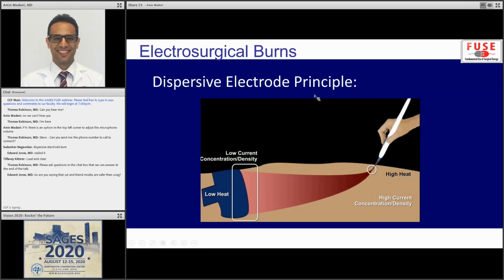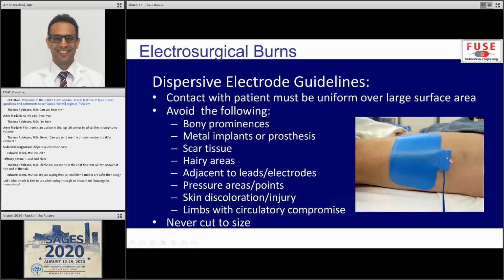The dispersive electrode is designed with a large surface area to create low current density because the current has to go through it. You don't want any thermal effect here, so you want this to have as high a surface area as possible. Things go wrong when this pad comes off. If you put it on a bony prominence, or on someone who has a lot of hair, it may not stick properly.